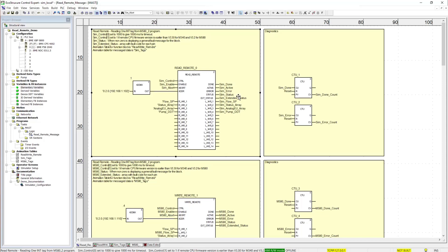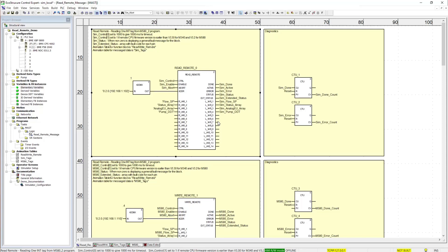The status, if there's a zero then the block is functioning fine. If it's anything but zero then there is an error, and we need to review that error in the help file. The extended status is the same as the status but for each one of these pins. If there's an error on any of these pins, it will tell you which pin has an error and what that error is.